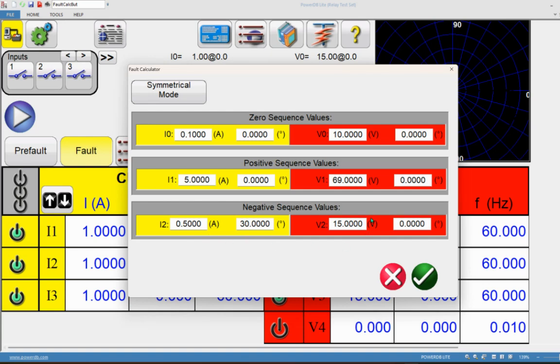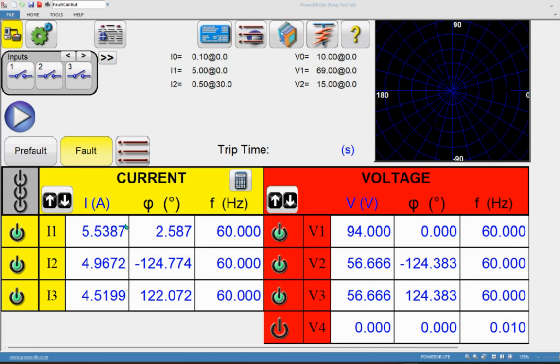To calculate the resultant values — recall VA = VA1 + VA2 + VA0 — you have to add all positive, negative, and zero sequence voltages for each phase. For current, IA is computed by summing contributions using the a-squared operator formulas. To avoid that cumbersome activity, this tool lets you simply enter positive, negative, and zero sequence values, click OK, and the fault calculator automatically calculates the required output values.